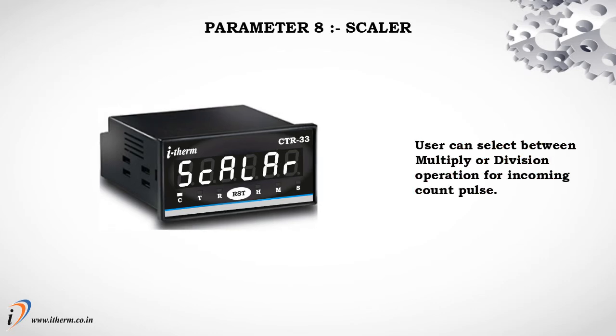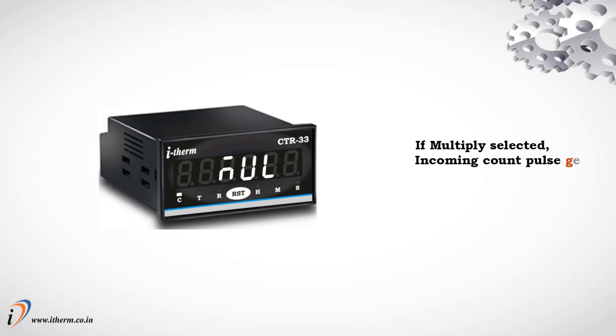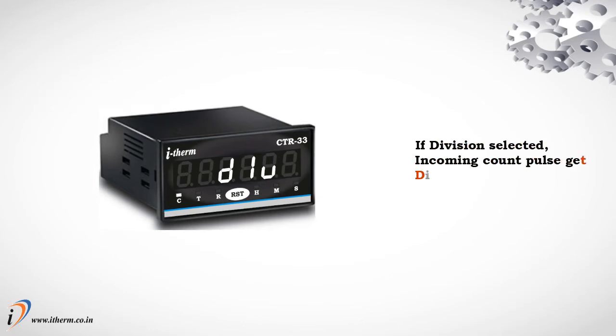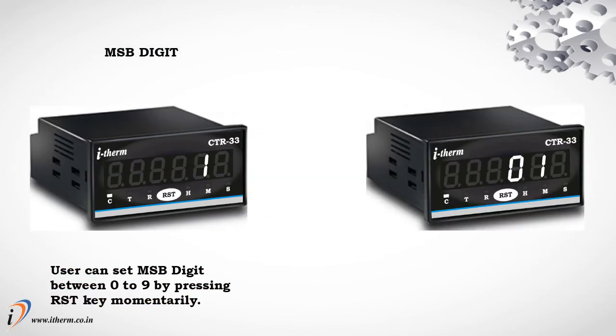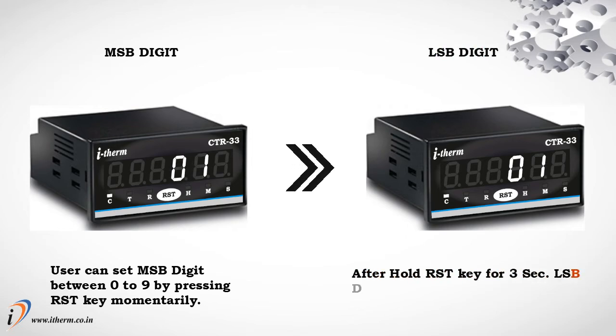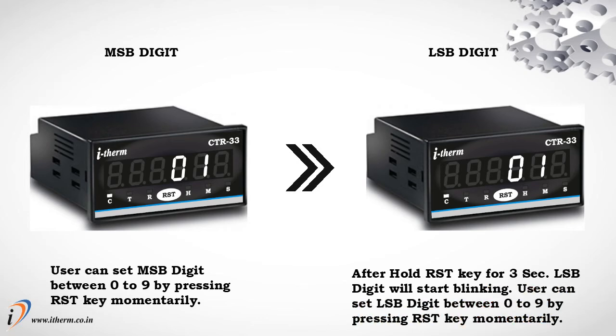Parameter 8: Scalar. The user can select between multiply or division operation for the incoming count pulse. If multiply is selected, the incoming count pulse gets multiplied by the factor selected by the user. Parameter 9: Scale Factor. This sets the factor value for multiply or division. The minimum factor value is 1 and the maximum is 99. The user can set the MSB digit between 0 to 9 by pressing the reset key momentarily. After holding the reset key for 3 seconds, the LSB digit will start blinking and can be set between 0 to 9.